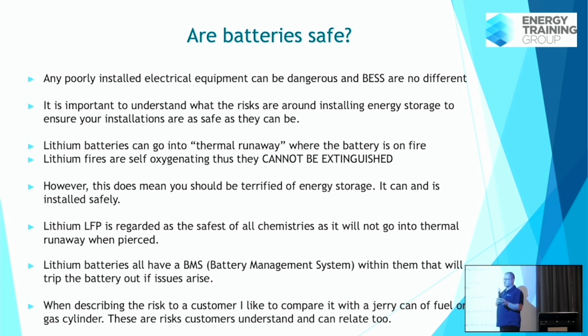Usually when a battery starts to get unsafe, it will start to swell and discolour before it gets to a point where it bursts into flames. I've only seen that on very early lithium batteries, and for at least 18 months I haven't seen any issues. Wherever there's been issues, the batteries have been turning themselves off - the firmware's doing its job, disconnecting the battery, and ensuring it doesn't deep discharge or overcharge, because both of those things will cause an issue.